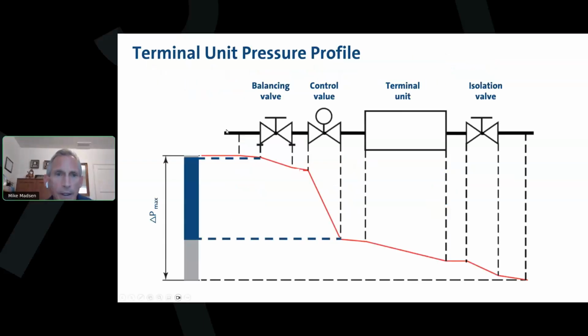So when you look at a linear version of a zone, you've got your balancing valve portion, you've got your control valve portion, you've got your air handler unit, and you've got your isolation valve. And then you'll see the big pressure drop here between the balancing valve and the control valve. This big pressure drop is what we want to eliminate. And we need this pressure drop to get what they call good valve authority. And so what is valve authority?